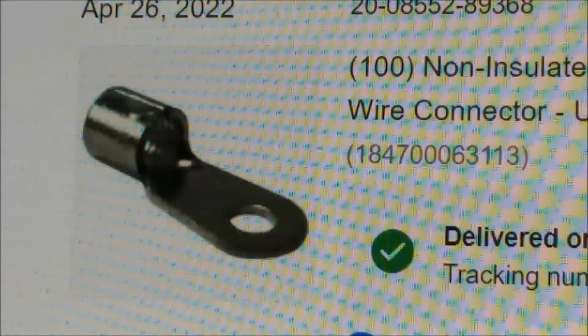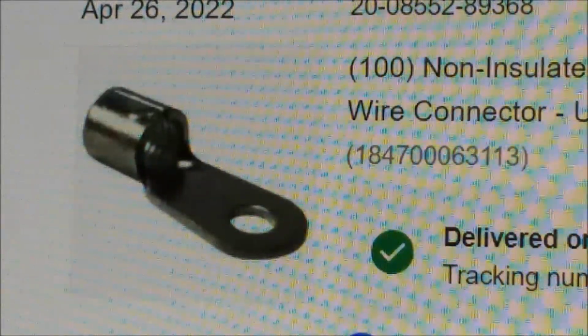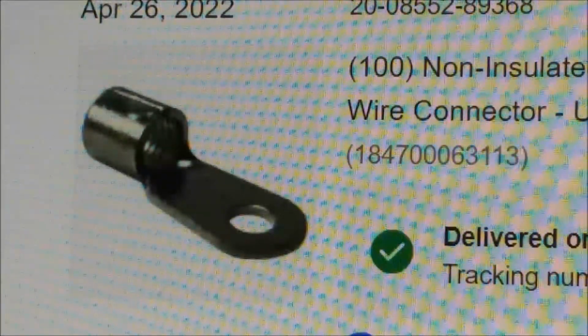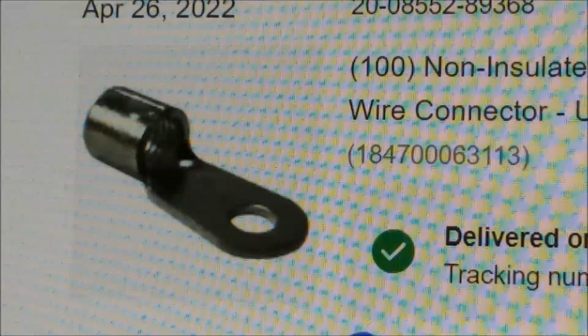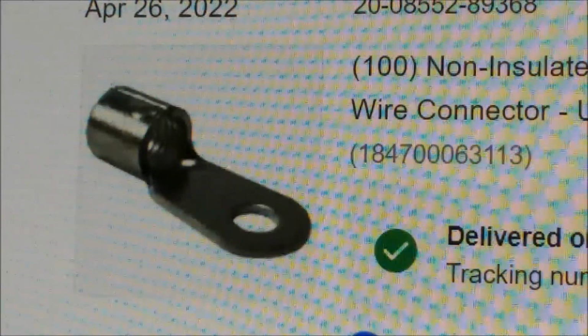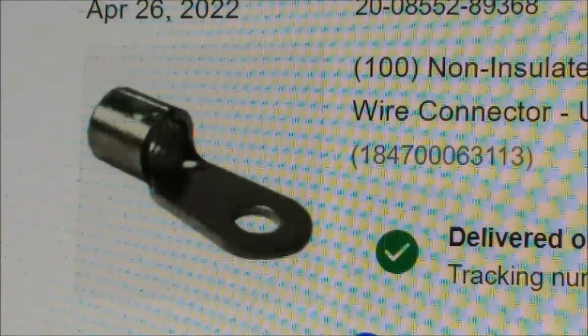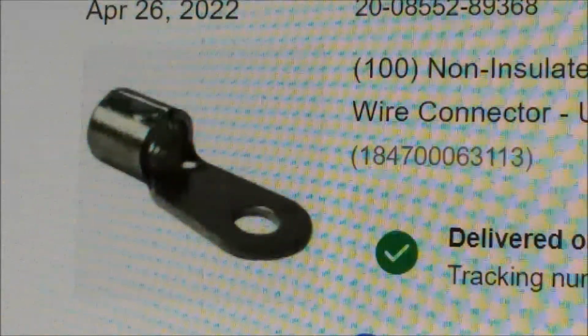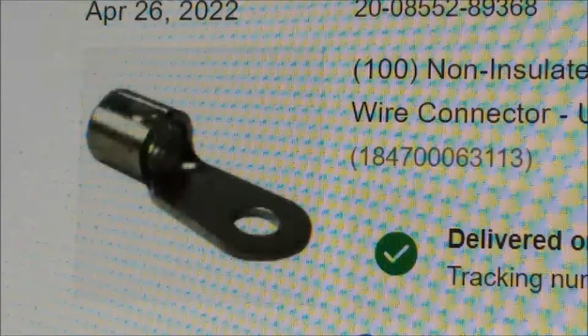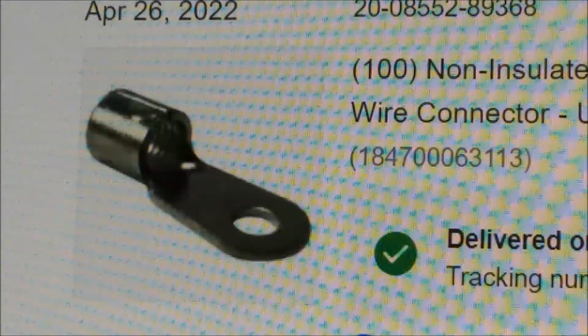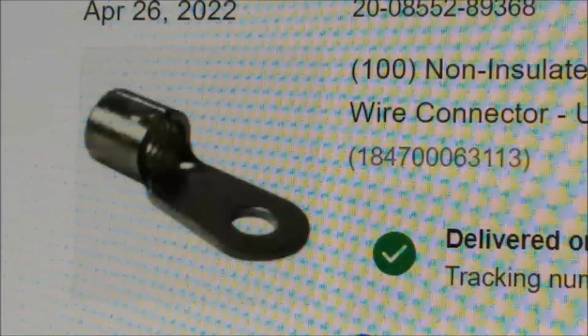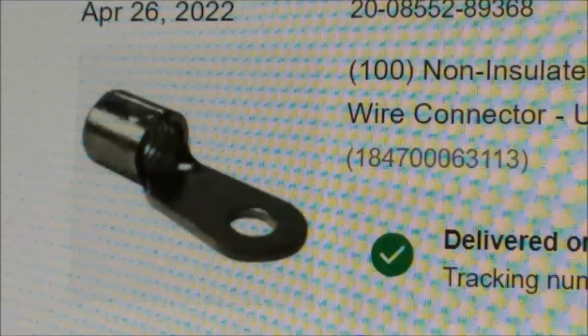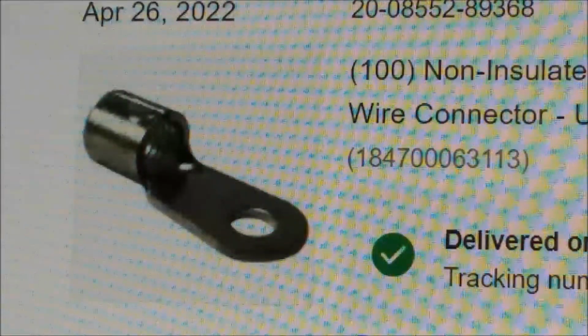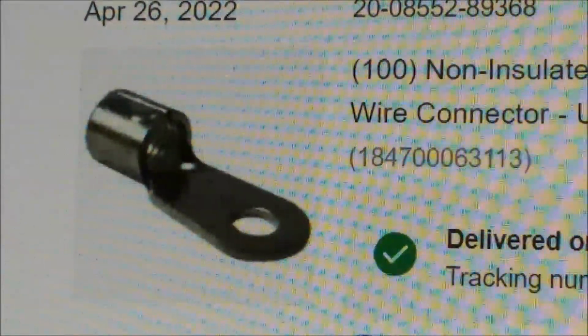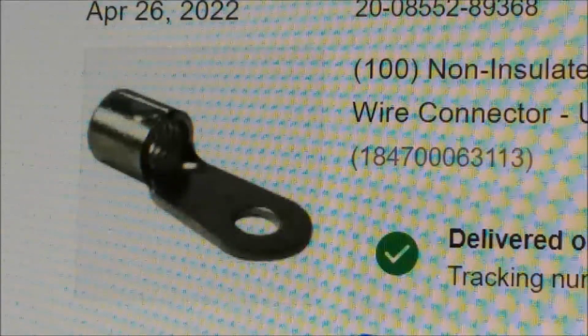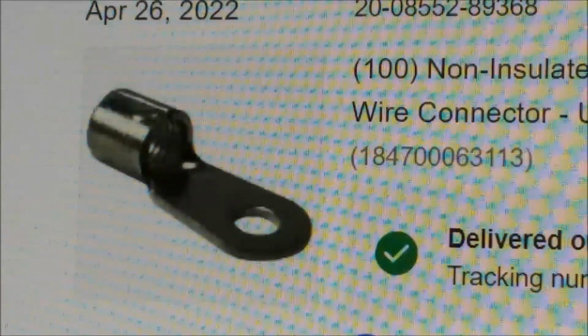We're going to connect a lot of this with 10 millimeter squared wire. That'll either be THHN for inside of panels and general utility inside the power room, but outside it'll be 10 millimeter squared PV wire. It's cross-linked polyethylene, electronically cured or something, with two layers of insulation and tin copper for the conductor. We're using single conductor. You have to downrate the size if you use the two-conductor kind that looks like Romex.